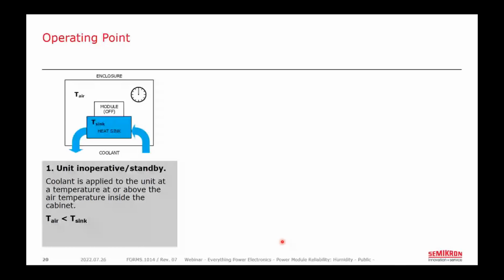So the first one is operating point, and operating point refers to the electrical loading of a system, and in turn, the thermal load on the heatsink, module and surrounding air. What we have here is a power semiconductor module mounted to a heatsink, inside an electrical enclosure, and the coolant could be either air or water flowing through or over the heatsink. In this first state, the system is not operating, and ideally this coolant is at or above the ambient air temperature inside the cabinet to prevent the dew point problem we were discussing earlier.